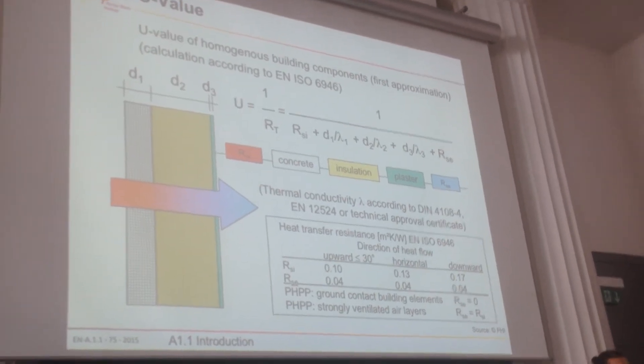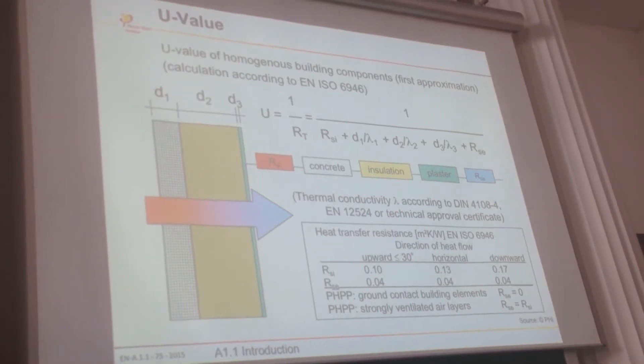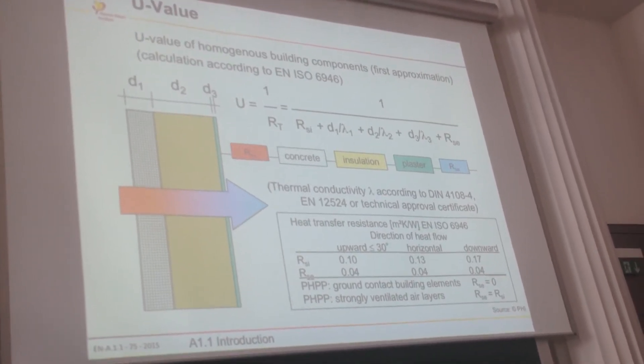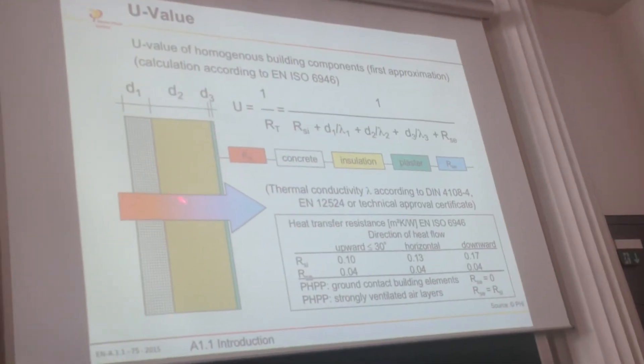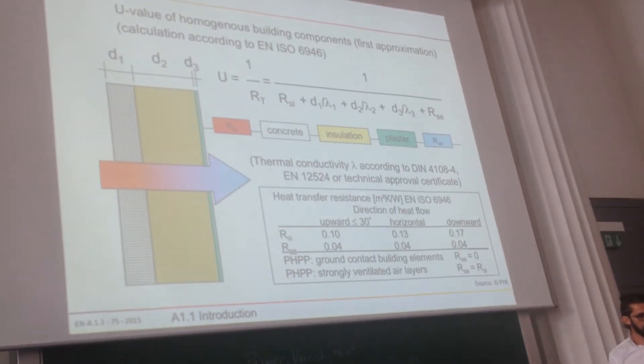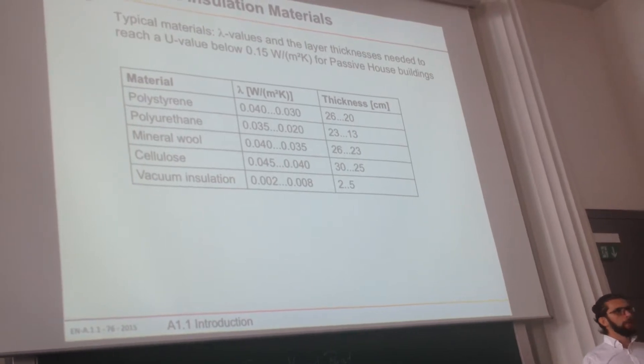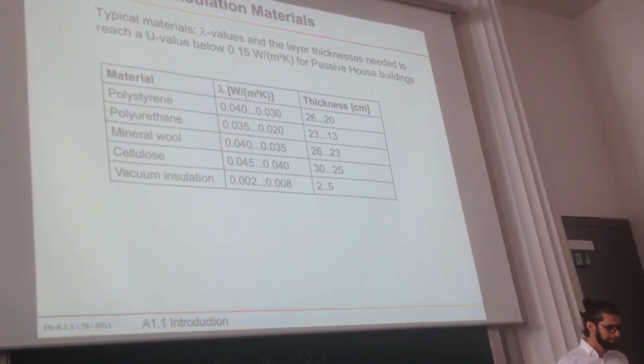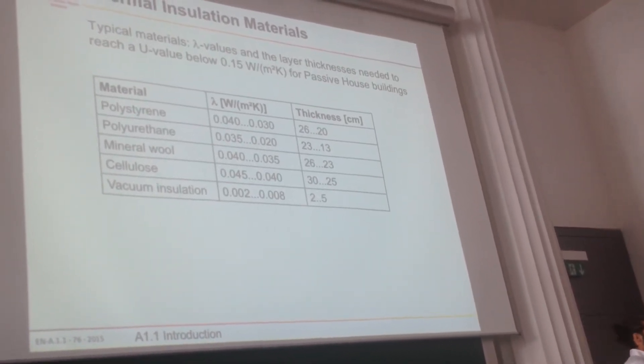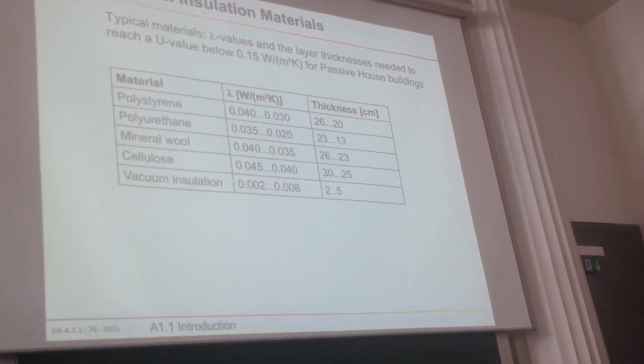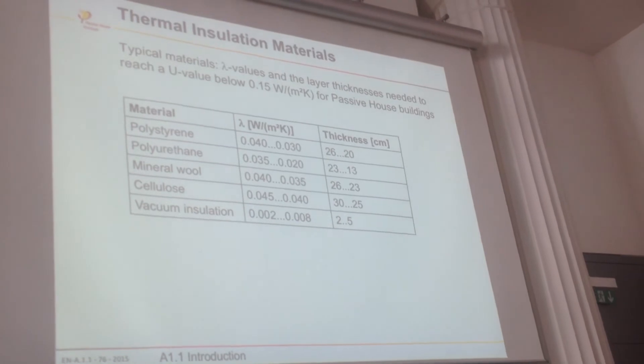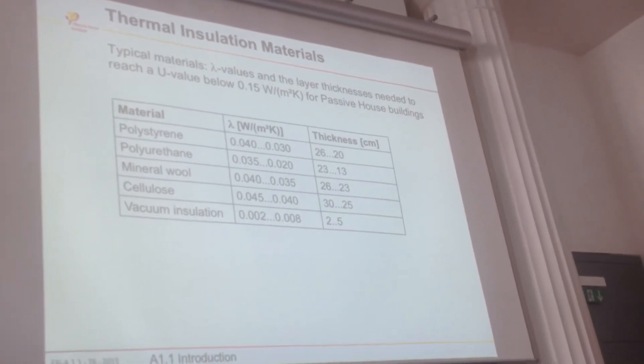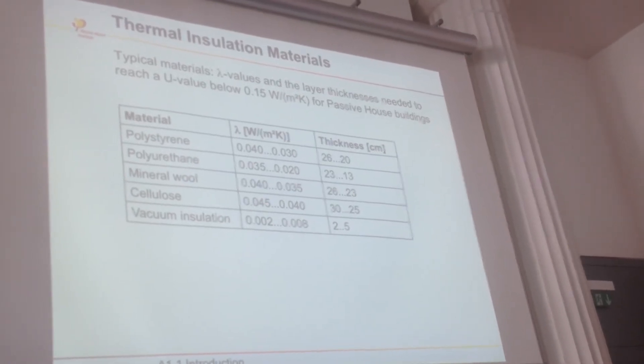More in detail — if somebody wants to calculate it, I think this afternoon I will do some exercises. It looks maybe a little complicated but it's quite simple. It's always thickness divided by lambda value, and at the beginning and the end it's inside and outside surface resistance factors. That's how we calculate U-values. The sum of all my losses — I have to calculate not only area losses but also tightness. If my tightness is not good enough, I will lose a lot of energy through infiltration.